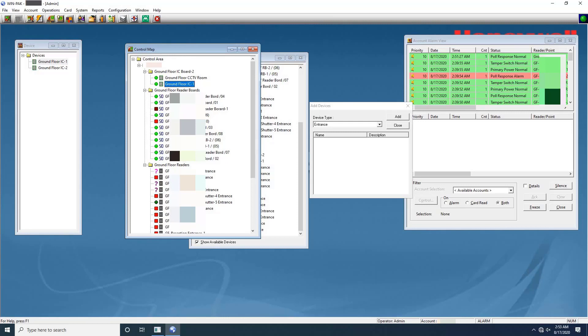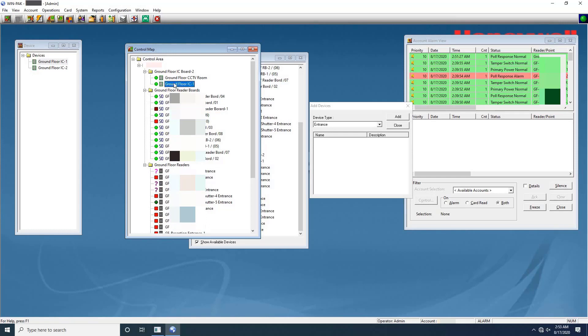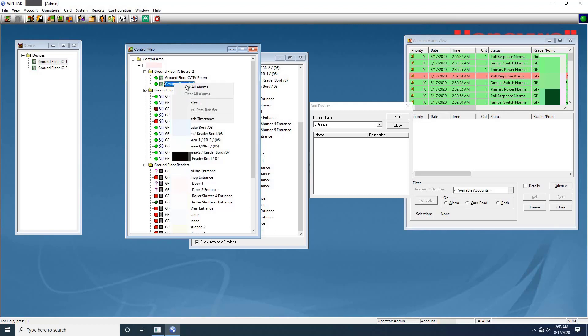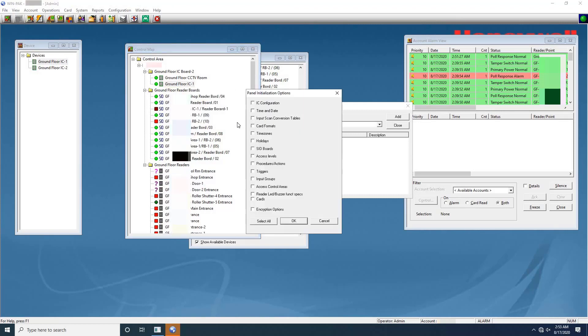As you can see, the added IC is in normal status. It means it's communicating with WinPak Server. But SIO Board is alarm condition and the card readers are unknown status. To solve this issue we have to initialize the IC. To initialize an IC from the Control Map, right click on the P Series panel in the Control Map tree and select Initialize. The Panel Initialization Options dialog box will appear. To send all types of information, click Select All button. Then click on OK.